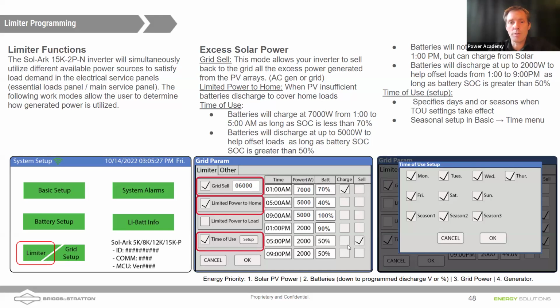So for that customer that called in earlier, he wants to buy electricity at nighttime. So he would enable this and set up these different times. What this does is it allows the battery to charge from the grid between the hours of 1 a.m. and 5 a.m. whenever the battery is less than 70% state of charge. And it will charge that battery up to 70% state of charge from the grid at 7,000 watts until it hits 70% state of charge.